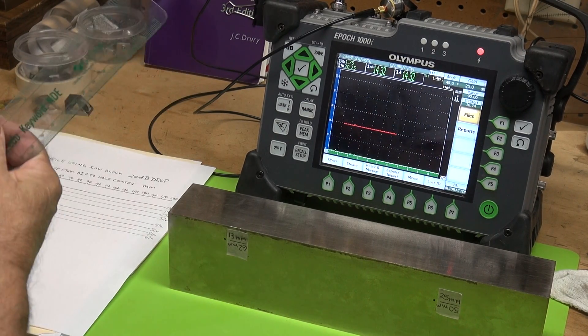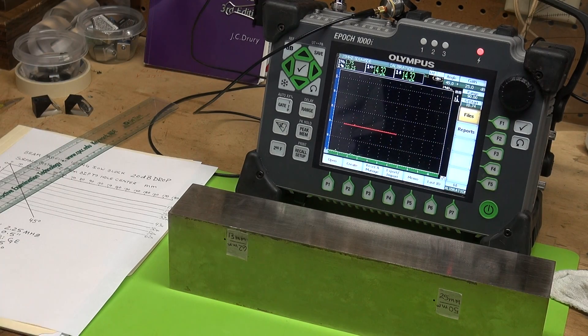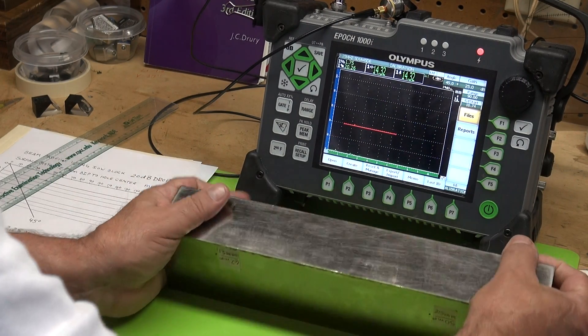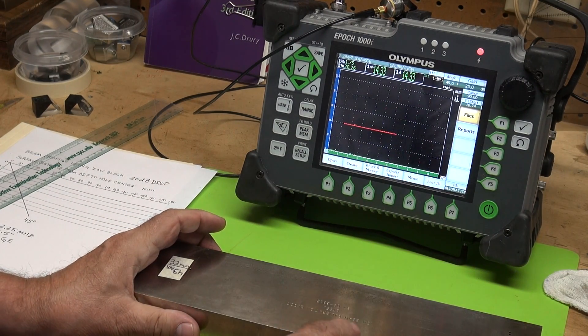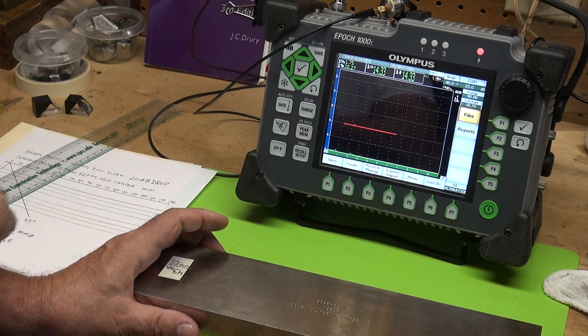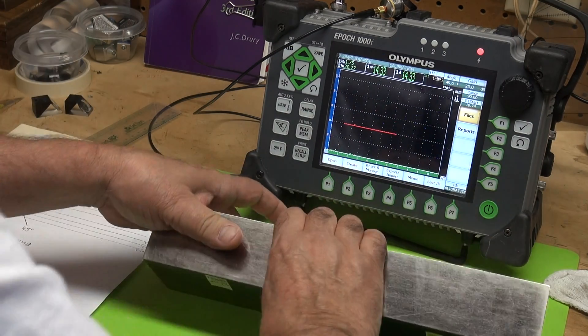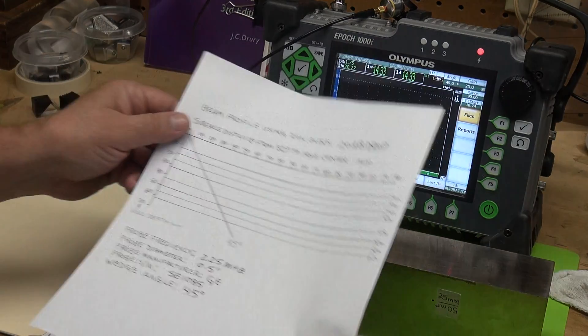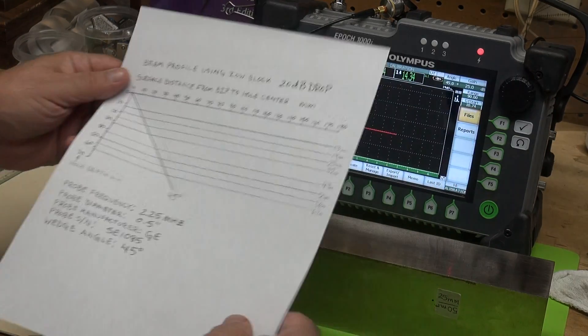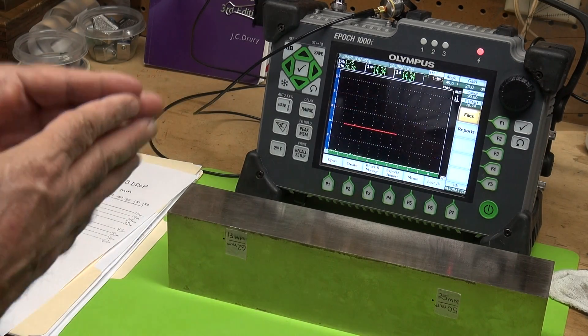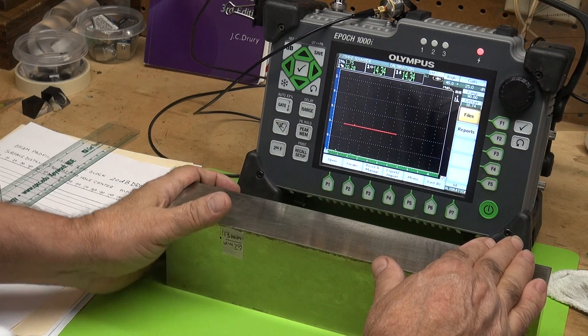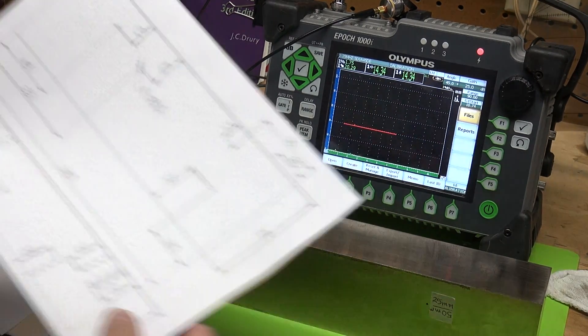I want to demonstrate a beam profile of a transducer and how we come up with a beam profile. We use an IOW block — this is an IOW beam calibration block and it's designed to plot the beam spread of your transducer. Your transducer isn't a laser beam; it's actually kind of like a flashlight beam and it spreads with beam divergence as our distance increases.